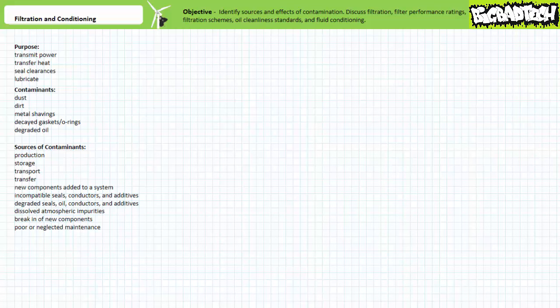Sources of contaminants include production, storage, transport, transfer, new components added to a system, incompatible seals, conductors, and additives, degraded seals, oils, conductors, and additives, dissolved atmospheric impurities, break-in of new components as manufacturer tolerances are worn away, and poor, neglected maintenance.